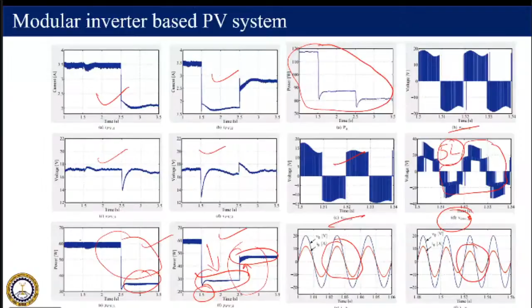So for PV mismatch, when we have a 60 watt and 85 watt panel, you can see even then the MPPT controller is able to extract the maximum power from each module. One module operates at 60 watts, which is its maximum power, the other at 85 watts, which is again its maximum power. So even with a PV mismatch, the controller is able to do its job. This is the THD and power graph.